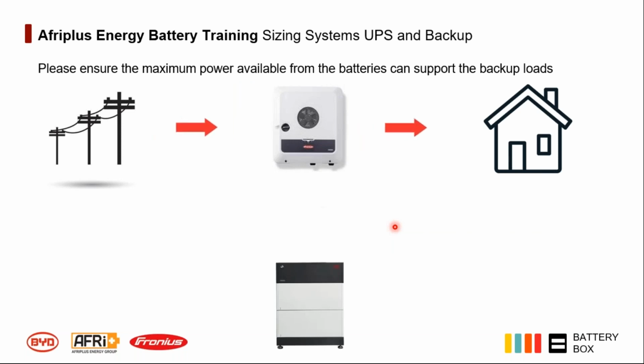Here we've got the size of your battery backup systems. Here we've got an example of your backup, and if you draw more loads than your battery can supply in backup, your system will turn off. So it's very important to keep in mind when planning your backup systems to ensure that the amount of energy your battery can supply is more than what your loads are going to draw. Because if your loads draw more power than your battery can supply, the system will unfortunately turn off.